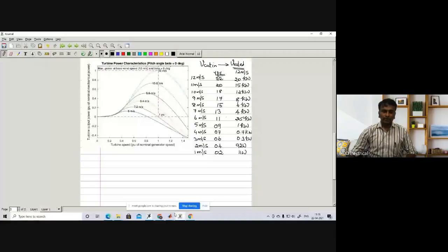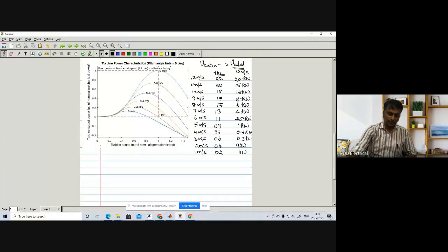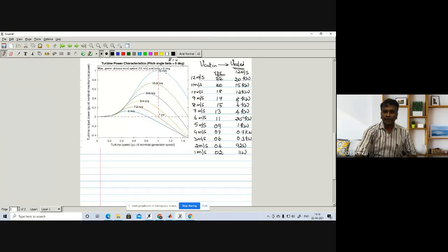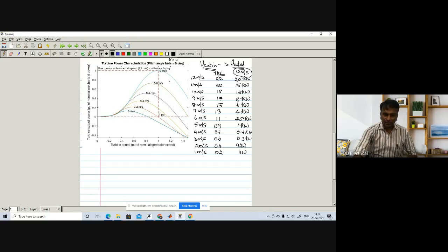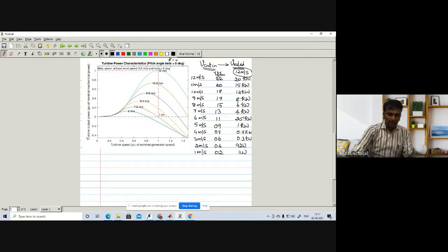Let me share my presentation. The wind turbine characteristics are formed at pitch angle beta equal to zero degrees. The rated wind velocity V_rated is chosen as 12 meters per second. At 12 meters per second we are getting rated power in per unit and rated speed in per unit.